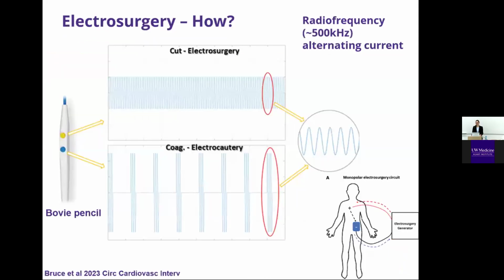Well, the surgeons listening or in the room know that the application of monopolar radio frequency current on a continuous basis focally can achieve tissue cutting by vaporization of intracellular water molecules. On the left side of this figure, that's the Bovie pencil, the yellow button achieves continuous current application. That's in contrast to the coagulation mode, which is achieved by pressing the blue button on the Bovie pencil, again familiar to surgeons, which delivers intermittent pulses of current, and that's primarily used to coagulate tissues.